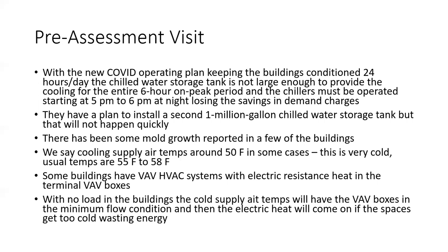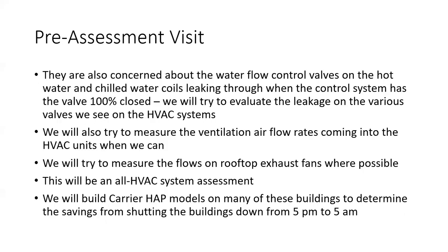Let's see. Yeah, so I think I pretty well talked through all of the points on this slide. They're also concerned, oh yes, the hydronic system, which is the chill water and the hot water that's supplied to the coils that actually does the conditioning of the air. Okay, so they think that they have a lot of valves that leak through when they're supposed to be closed.